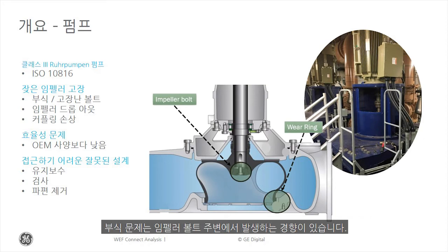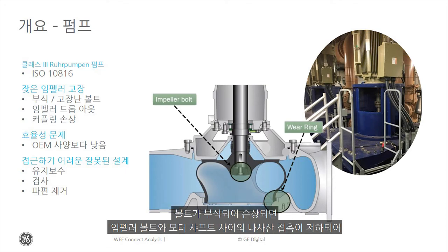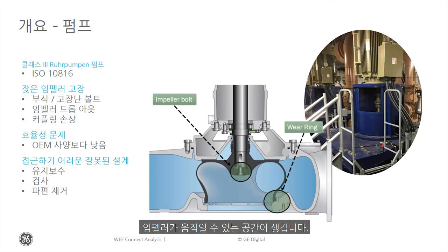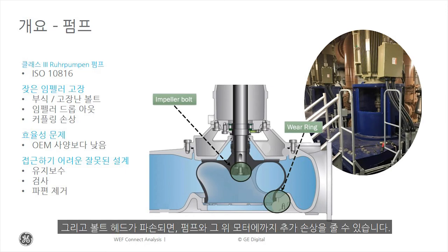Corrosion problems tend to manifest around the impeller bolt. As the bolt corrodes and becomes compromised, the thread contact between the impeller bolt and the motor shaft degrades, allowing the impeller to have some wiggle room to move around. When the pump experiences a vibration event caused by some unexpected foreign material in the flow, the already corroded bolt head can snap off.